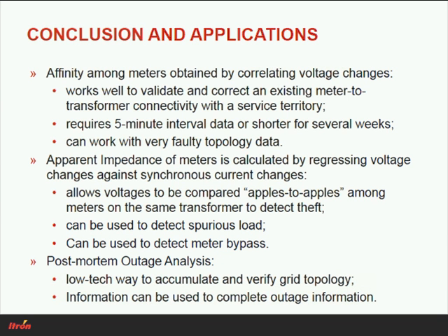Were impedances calculated for different services consistent, or was there a wide range? I showed a chart on the range early on. Most of them tend to be between about 20 and 100 milliohms. Those that were higher would frequently be where the correlation wasn't very good, so you can't really pay too much attention to it.